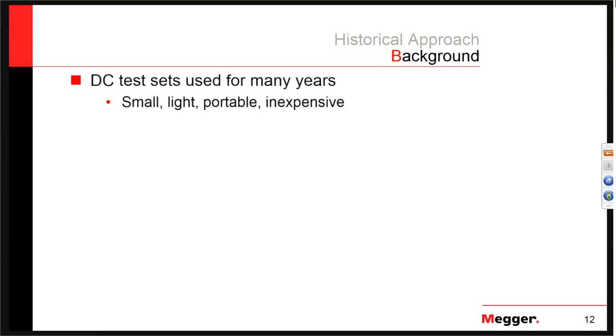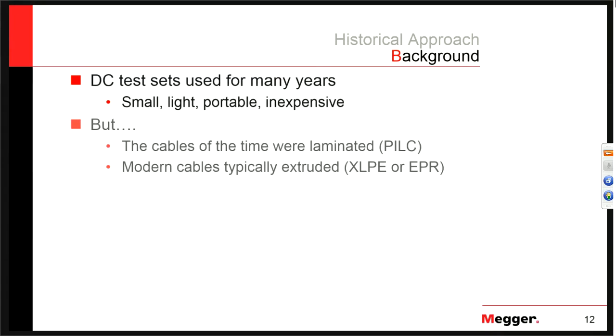Historically, for many years, DC test sets were used. They were small, light, portable, and inexpensive — checked all the boxes. But the cables at the time were laminated PILC cables. The extruded cables that came later develop a trapped space charge. If there's any imperfection in the insulation — a small speck of dirt, a small air void — the electrons moving in one direction with the DC test will gather at that imperfection.